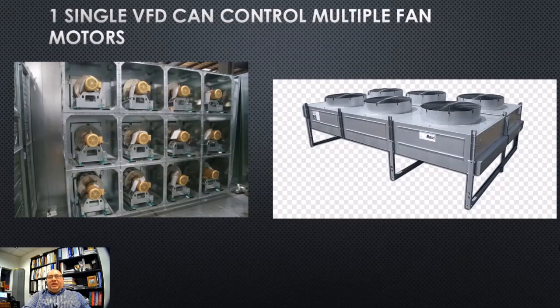So we usually think of one VFD per motor, but things are changing now. You could get what's known as a fan bank, depicted here on the left, where instead of having one or 2 big indoor blower motors, now you have a wall, called a fan wall, with multiple smaller motors in the airstream. So actually one VFD can control a few different motors, believe it or not, and they also do that in refrigeration. When you're doing that, make sure the horsepower of each motor is added up for a total horsepower, and that drive would have to be able to operate that total horsepower. So basically it's not one VFD per motorized device anymore. There are some loopholes to this, and it's pretty neat how the industry is changing. But you can control multiple motors with one VFD drive if it's sized correctly.